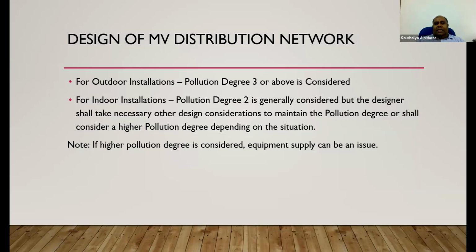For outdoor installations, generally pollution degree 3 or above is considered as required. For indoor installations, pollution degree 2 is generally considered, but the designer shall decide what level of pollution will be present. Either the designer should take precautions to lower the pollution degree from degree 3 to degree 2, or shall consider a higher pollution degree depending on the situation. But if you are to find indoor equipment, you may find it difficult to source some of the equipment if you are going for higher pollution degrees or pollution categories. So that is to be kept in mind.